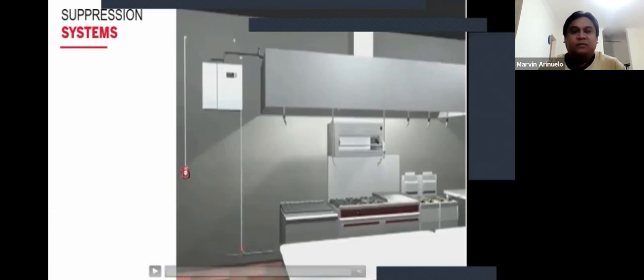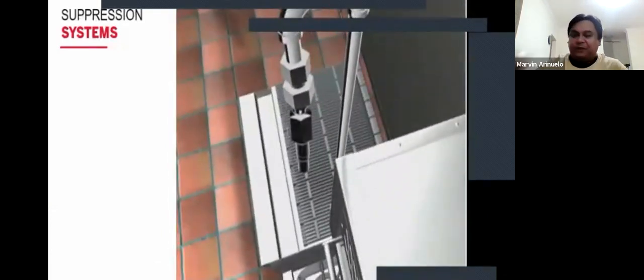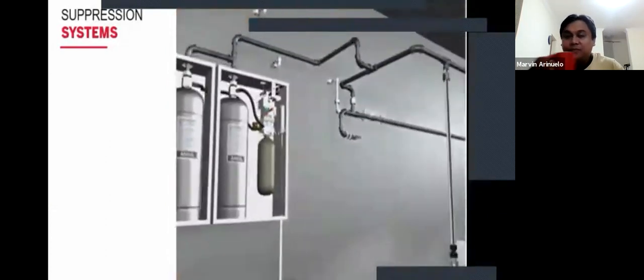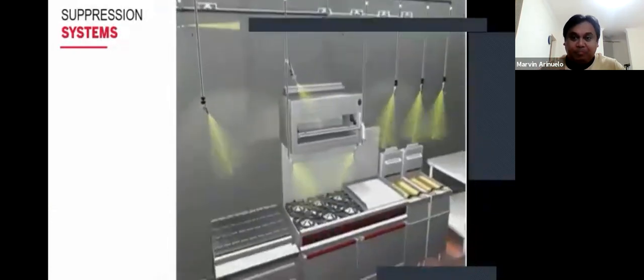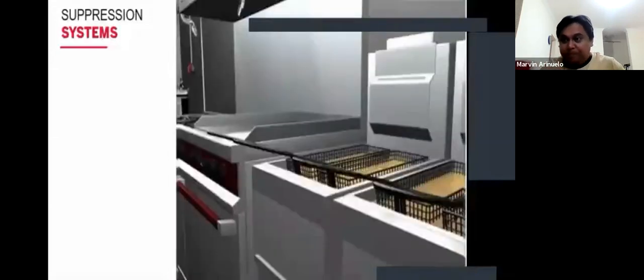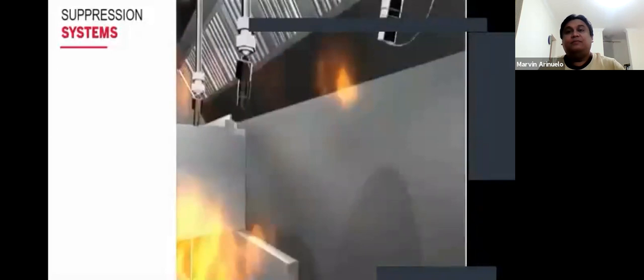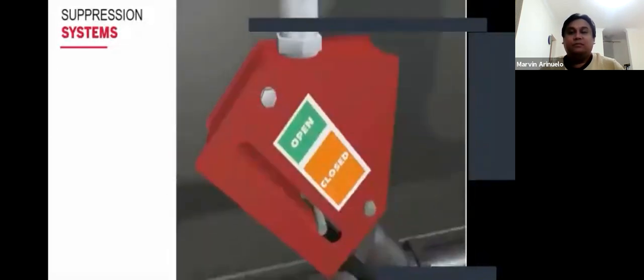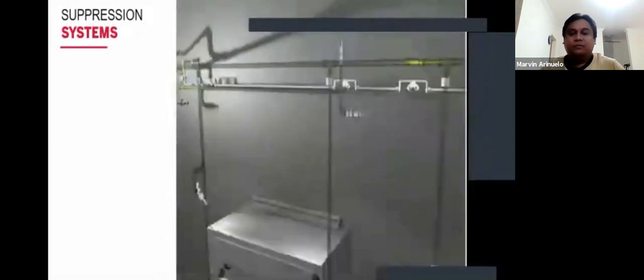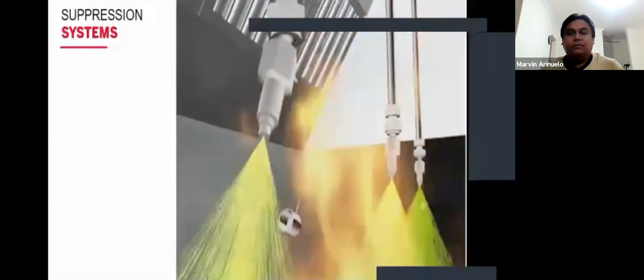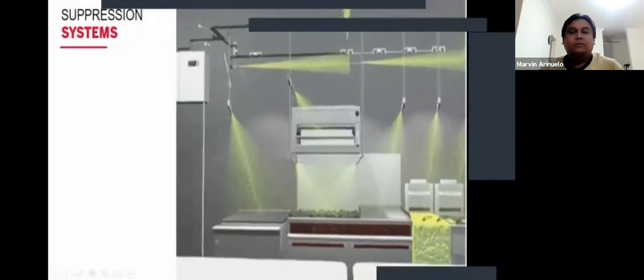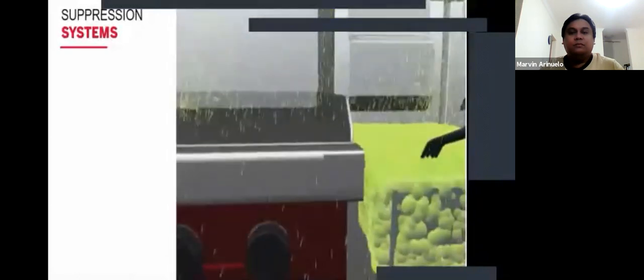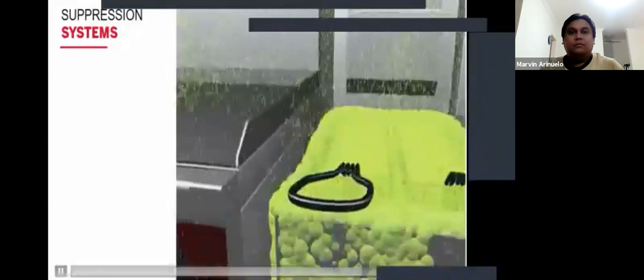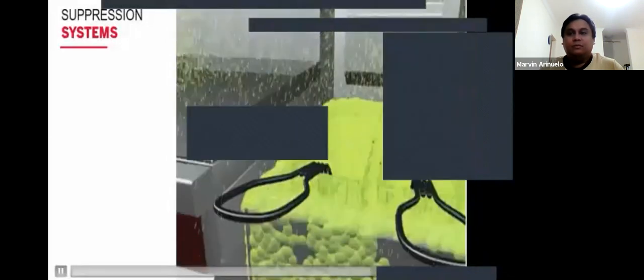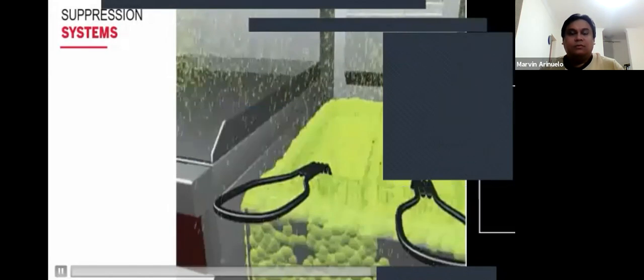In commercial cooking operations, fixed fire suppression systems are the primary means of fire control, with portable fire extinguishers secondary. Fire detectors automatically activate the fixed fire suppression system and must be applied at a rating and location that permit them to respond promptly to any abnormal temperatures in the effluent from the cooking operation. Wet chemical systems or water mist suppression systems are the most common types used for fire suppression in industrial kitchens. Automatic sprinklers are also used as indicated by codes and standards. Large-scale food production lines frequently use carbon dioxide systems because carbon dioxide is a clean agent, which reduces the amount of cleanup and subsequent production downtime. These fire suppression systems require special training of kitchen workers so that they do not inadvertently exacerbate a fire event.